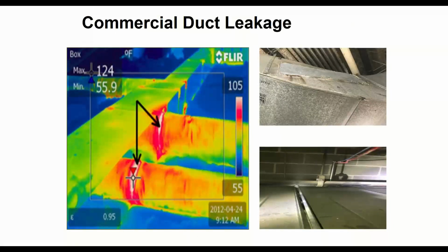For those that don't like numbers and metrics, we got a couple visuals on here. So you can kind of see, this is an infrared thermal camera on the left. I believe this photo was courtesy of Airway Systems. So I got to thank the people that I literally steal from. But you can see here the temperature differences with the thermal camera and where these two ducts connect. In this case, it's two flex ducts running off to diffusers. So commercial buildings, we don't typically use flex duct, except for that 4 or 5 foot distance from the main duct over to the diffuser. And you can see here, when things aren't connected properly, which is very frequently the case, you end up with duct leakage. The flex duct itself doesn't typically leak, nor does sheet metal duct. It's all the connection points. That's always the problem. Where things are connected in the field together, they're not tight. And you can see the gap here where I got warm air leaking out of this thing.